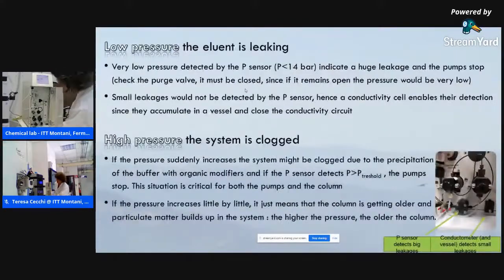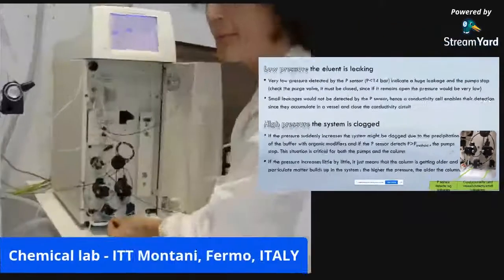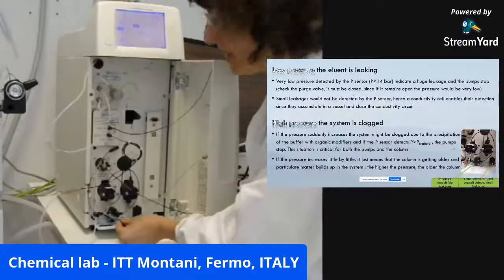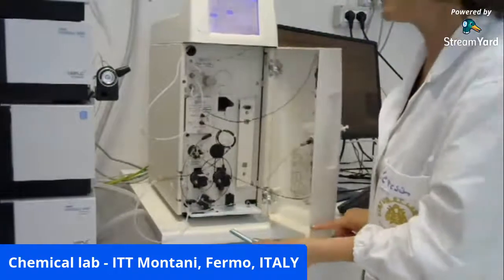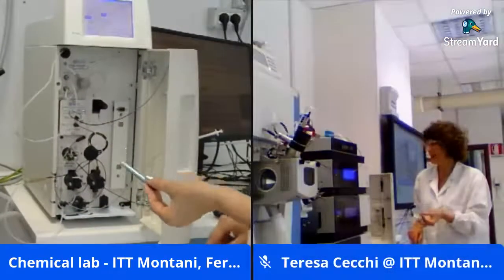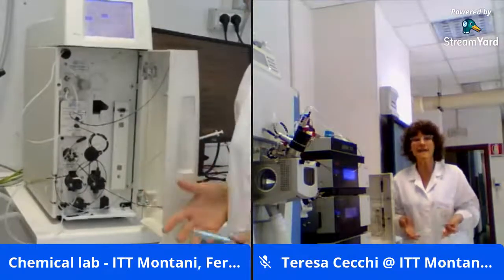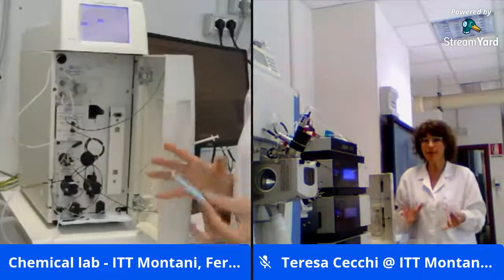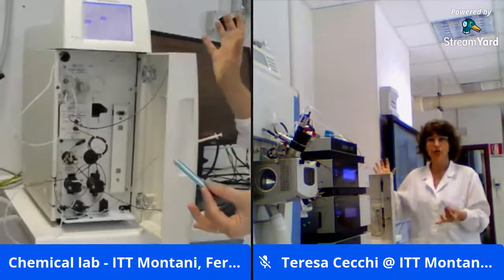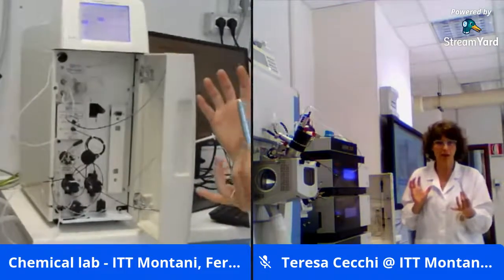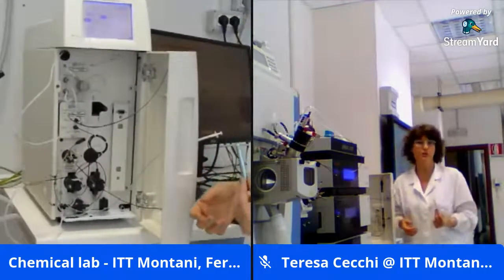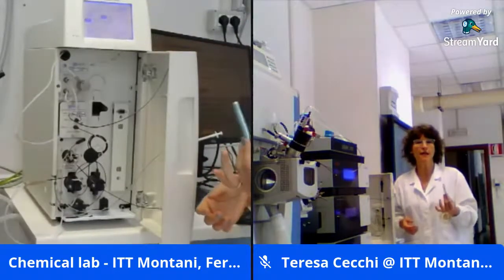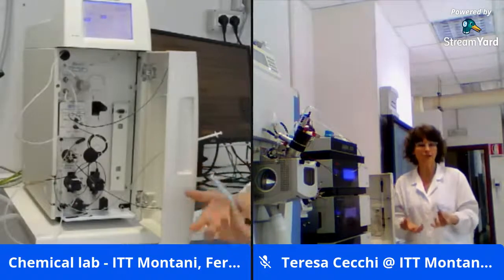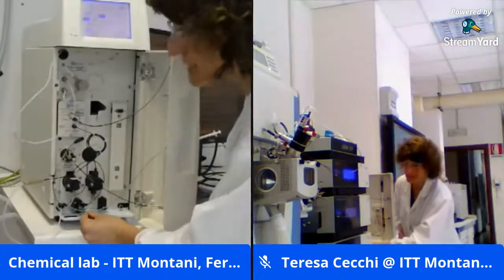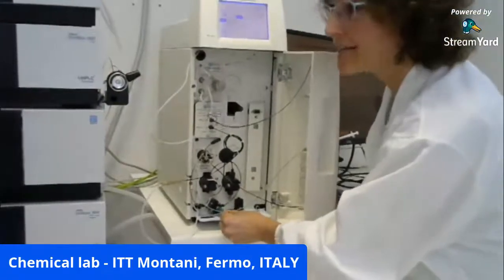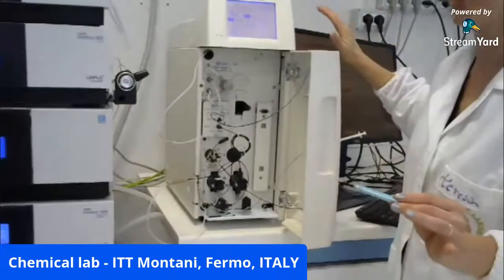What happens, the sensor of pressure here is very important because if the pressure increases very rapidly, probably the system is clogged. What might have happened? If we are not careful, the mixing of a buffer with ions, for example, with methanol, could provoke the precipitation of the buffer due to the lowering of the dielectric constant of the eluent. In this case, the sensor of pressure would alert us and the whole system would stop.